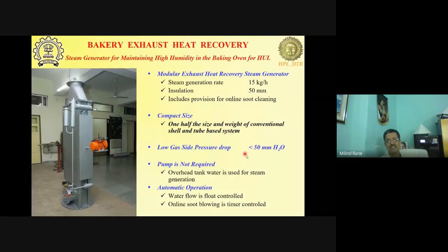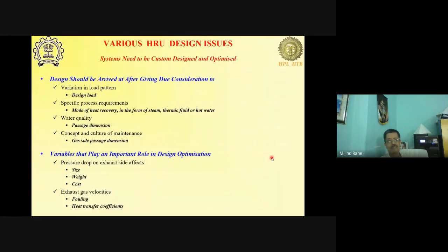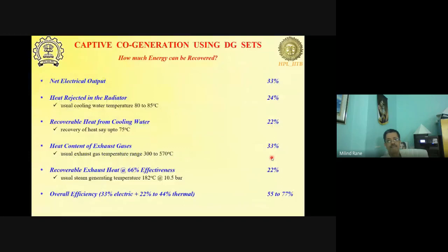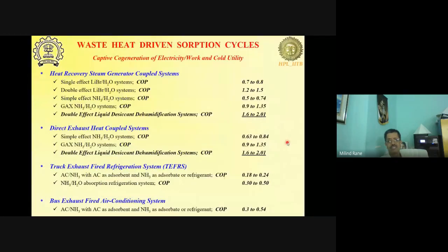Then exhaust heat recovery, we have discussed these also. Very low pressure drops across the flue gas side. These are some of the typical available heat in the generator, exhaust heat recovery, and so on and so forth. So if you recover from the generator exhaust heat, you have about 33% in the exhaust, you can recover about 22% from that. We have about 24% in the radiator hot water circuit, we can recover about 22% on this and so on and so forth. Okay.